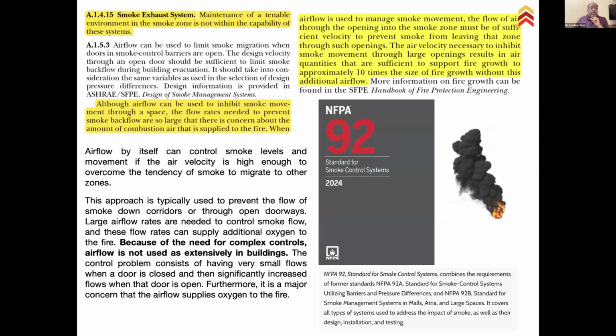Maintenance of tenable environment in a smoke zone is not within the capability of these systems. So, my dear friends, you may do as many air changes as you want, 12 air changes, whatever magic you try, there is no way that by virtue of a smoke exhaust system you can maintain tenability. So let's be very clear: if you are trying to have a smoke control system, tenability will not be achieved.